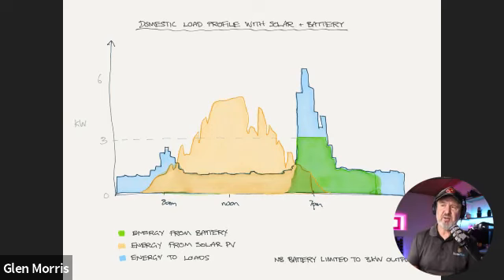So this is just showing the mix of energy over a 24-hour period in a typical home. And what I wanted to point out is that the energy coming from the battery is being capped at 3 kilowatts. And the reason for that is the size of the battery inverter. So just adding a battery system or AC coupled battery system to an installation doesn't mean that you will offset all of the customer's load energy, because the rate that it can deliver it at is limited by the inverter power of the battery inverter.